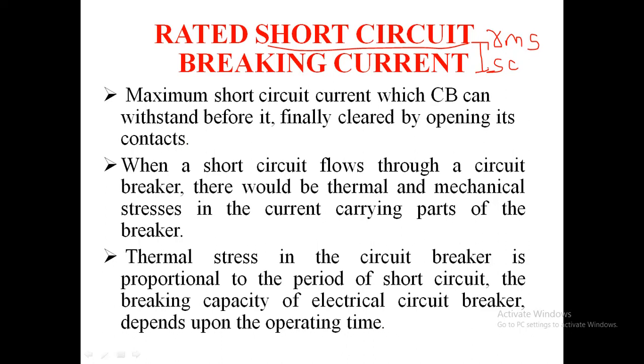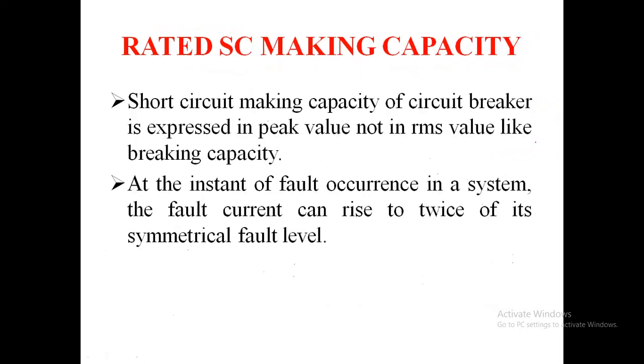The voltage appearing across the circuit breaker after arc quenching is the TRV, transient recovery voltage. The limit on breaking current is specified by the condition of this TRV and the power frequency recovery voltage, not the power factor. This limit is determined by carrying out the short circuit test, which means the breaking current can be expressed with two values.